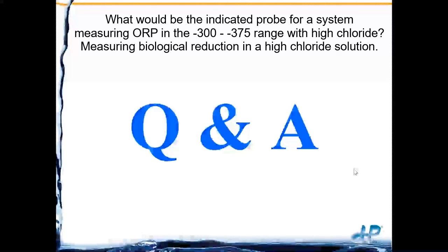Question: what probe is indicated for measuring ORP in the negative 300 to negative 375 millivolt range with high chlorides, measuring biological reduction? You'll need at least a double junction reference if using a traditional reference. It would also be worth considering whether pH compensated ORP is needed. If you simply have a high chloride solution, a double junction reference electrode with traditional KCl would be okay.